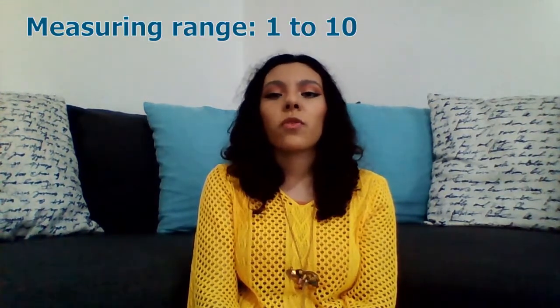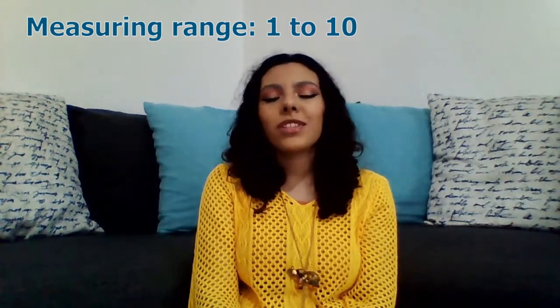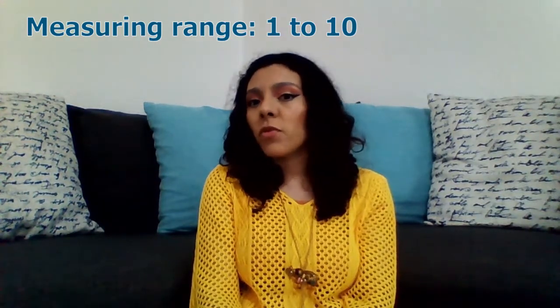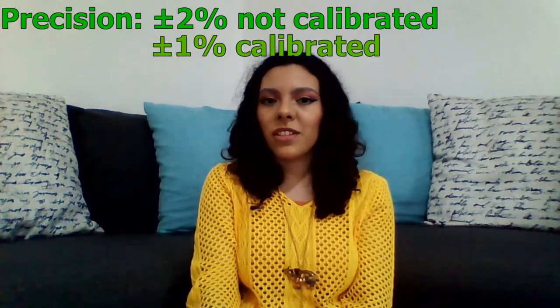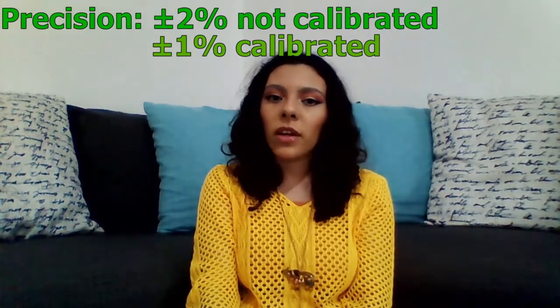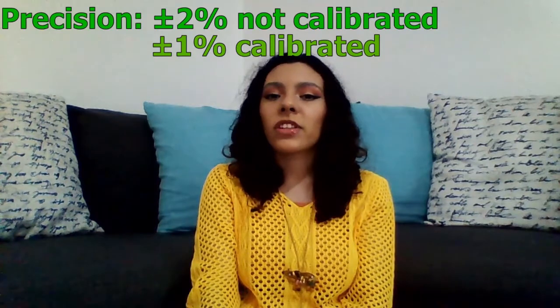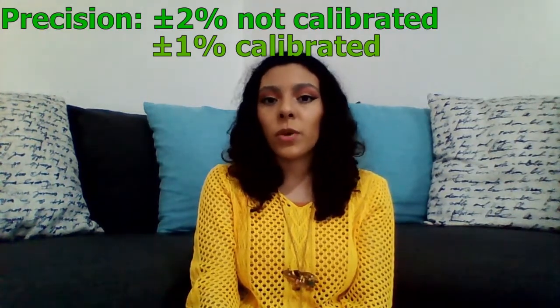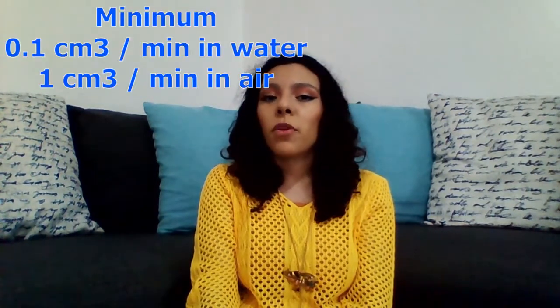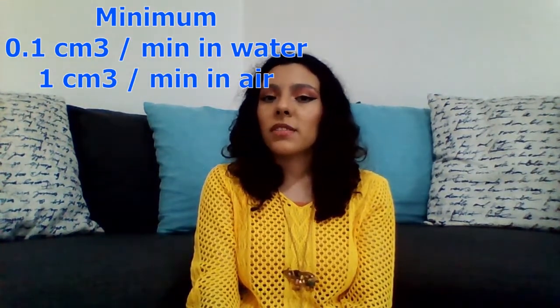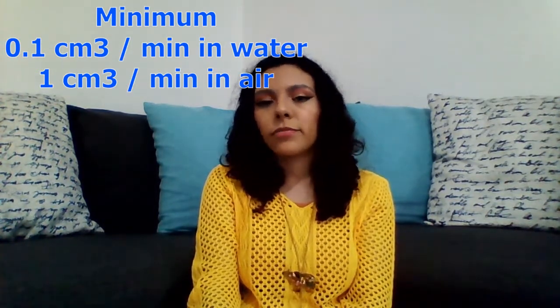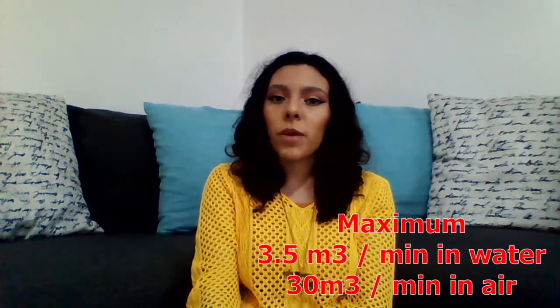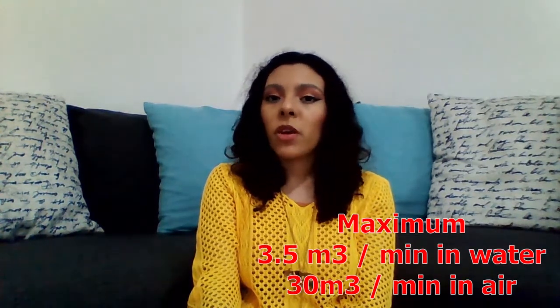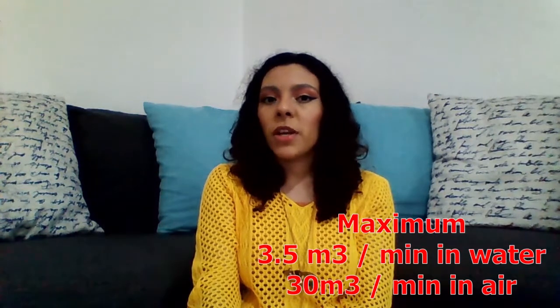The measuring range for rotameters is usually 1 to 10, which is the ratio of the minimum to maximum flow on a linear scale. Its precision is of the order of ±2% of the whole scale when they are not calibrated, and ±1% with calibration. Rotameters are suitable for measuring small flow rates, reaching minimum limits of 0.1 cubic centimeters per minute in water and 1 cubic centimeter per minute in air, while its maximum limits are 3.5 cubic meters per minute in water and 30 cubic meters per minute in air.